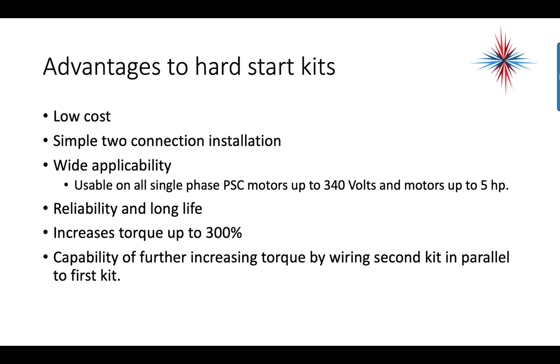Advantages of hard start kits: they're low cost with a simple two-connection installation. They can be used on all single-phase motors up to 340 volts and up to 5 horsepower. They're reliable with a long life and increase torque by up to 300%. You can even add additional torque by wiring second kit in parallel with the first kit.